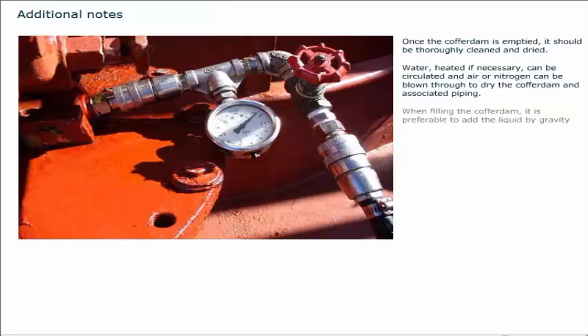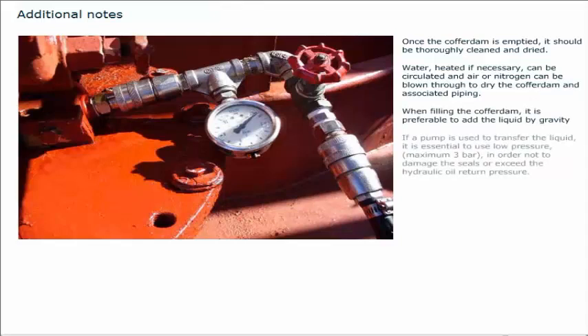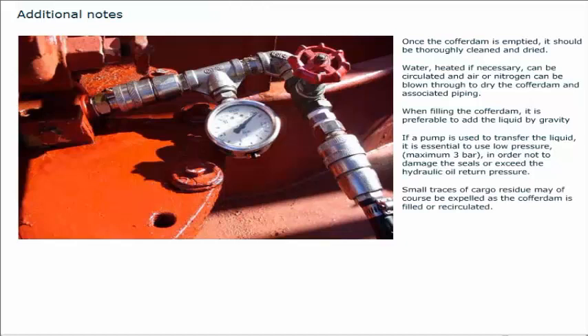When filling the cofferdam, it is preferable to add the liquid by gravity. If a pump is used to transfer the liquid, it is essential to use low pressure, maximum 3 bar, in order not to damage the seals or exceed the hydraulic oil return pressure. Small traces of cargo residue may be expelled as the cofferdam is filled or recirculated. The appropriate personal protective equipment must always be used.